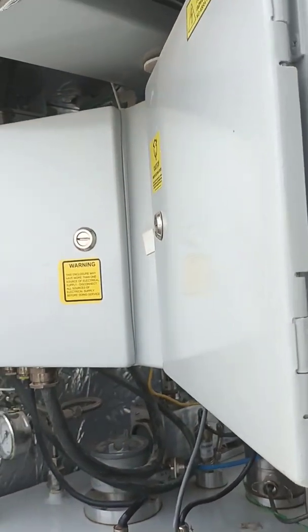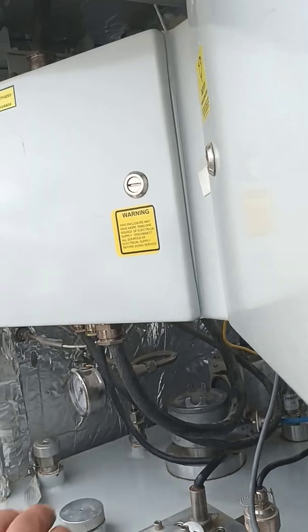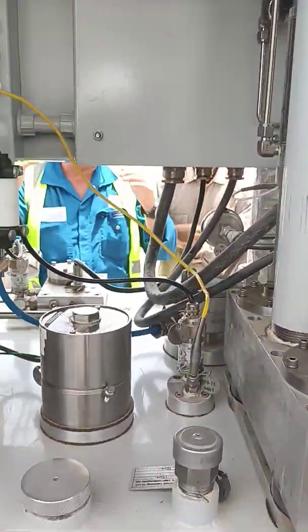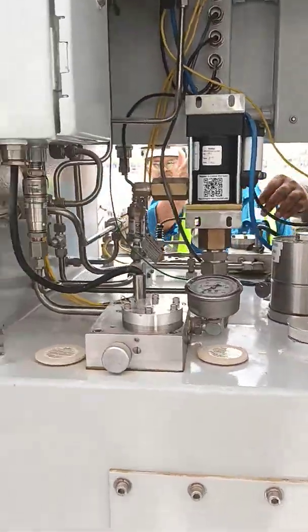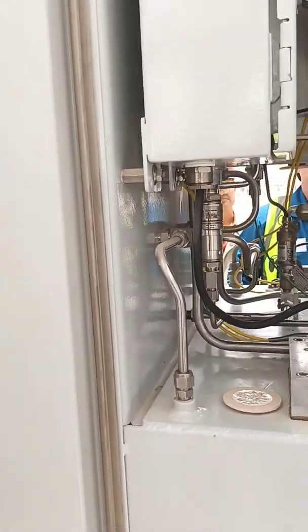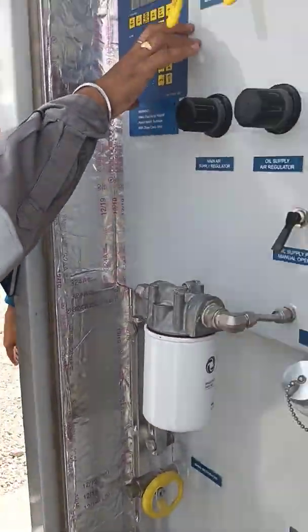You see that noise that you can hear now is the cooler. You can see it blowing here. It's the vortex that's on the top. Normally it will come automatically when it's more than 32 degrees inside the panel, that will open. So now it's blowing through. This one is working before. That is a main for the big tank. No issues.